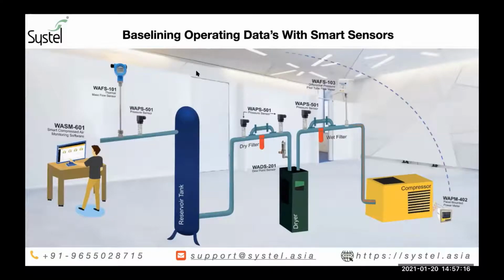Our first process in Industry 5.0 starts with baselining your operating data. With this, we connect our smart IoT based power meters on the compressors and differential pressure pitot tubes at your compressor outlets. These two sensors collect in real time the actual power that is consumed by the compressor, and the actual air output the compressor delivers. It consistently and continuously makes a relationship between the input power and output flow, and arrives at a specific energy consumption.